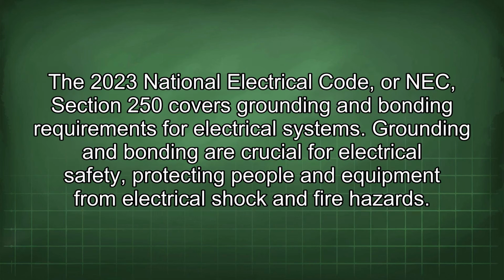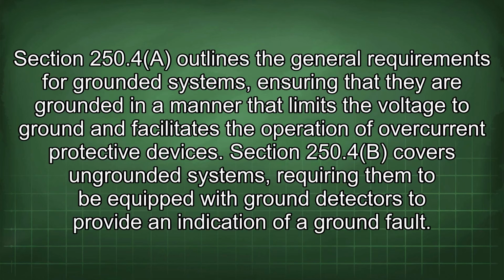The 2023 National Electrical Code, or NEC, Section 250 covers grounding and bonding requirements for electrical systems. Grounding and bonding are crucial for electrical safety, protecting people and equipment from electrical shock and fire hazards. Section 250.4 outlines the general requirements for grounded systems, ensuring that they are grounded in a manner that limits the voltage to ground and facilitates the operation of overcurrent protective devices.